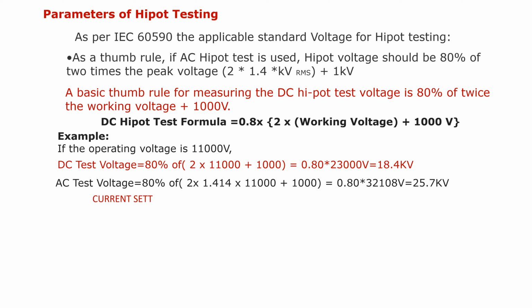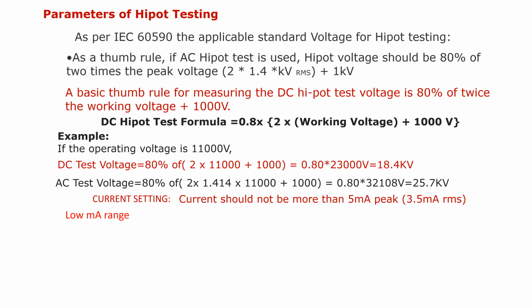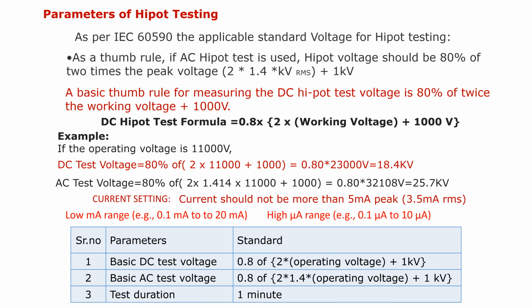Current setting should not be more than 5 milliampere peak, that is 3.5 milliampere RMS. Low milliampere range, for example 0.1 milliampere to 20 milliampere. High microampere range should be, for example, 0.1 microampere to 10 microampere. The thumb formula should be considered before starting the testing. Now, operating procedure.